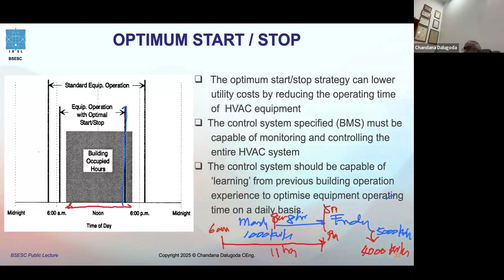No, 6 a.m. Monday, you pre-cool the building before occupation. Before all the computers and equipment are running, you pre-cool. The effect would be that this 5,000 can be dropped easily to 4,000 kilowatt hours. That is really happening. Now we are doing this in Ceylon Towers. One of the jobs that I just completed, Sampath Bank building, we are doing this. Enormous savings, optimum start-stop.